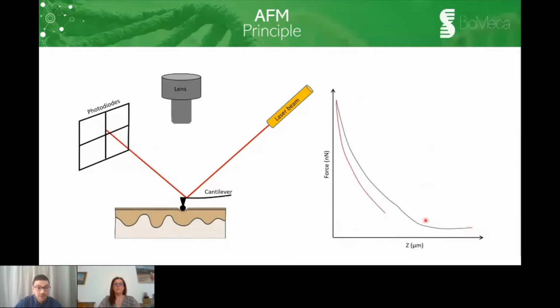And there are different parts on this curve. The first part here, very flat, corresponds to the cantilever not being in contact with the sample. Then with this exponential curve, which is the indentation of the cantilever in the sample, and the red curve with at the end the little shift, which is the retract curve, and this shift corresponds to the adhesion of the tip of the cantilever on the sample. And then we've got precisely the contact point that represents the point where the tip touches the sample here.